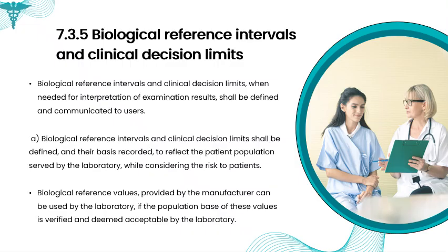Note: biological reference values provided by the manufacturer may be used if the laboratory has verified that the population base is appropriate and acceptable for its patient population.